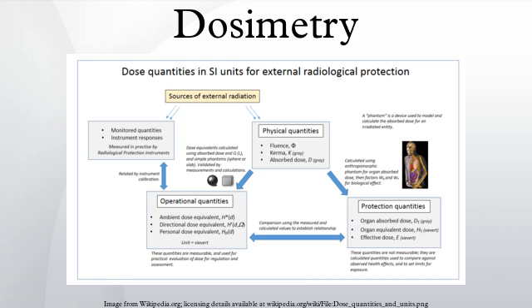Each measure is often simply described as a dose, which can lead to confusion. Non-SI units are still used, particularly in the USA, where dose is often reported in rads and dose equivalent in rems. By definition, 1 gray equals 100 rad and 1 sievert equals 100 rem. The fundamental quantity is the absorbed dose, which is defined as the mean energy imparted by ionizing radiation per unit mass of material. The SI unit of absorbed dose is the gray, defined as 1 joule per kilogram.